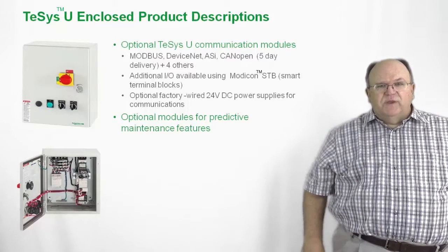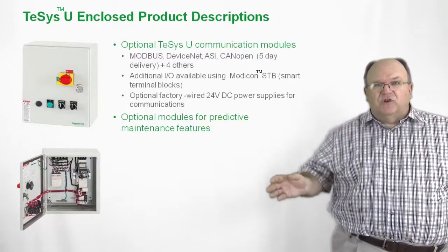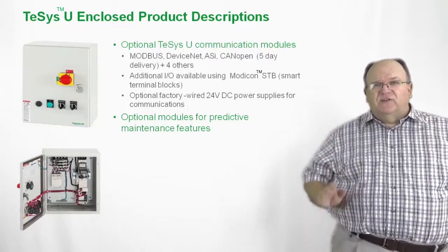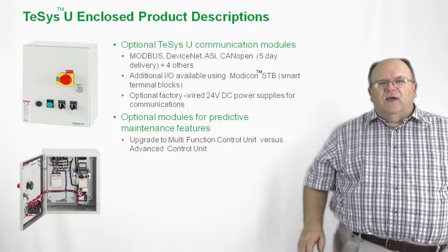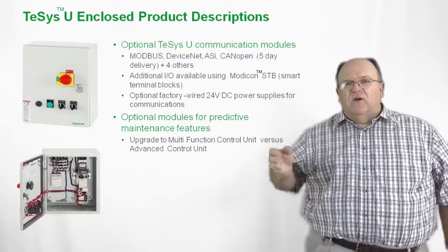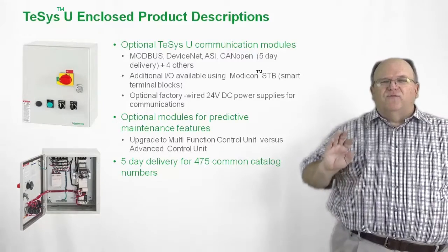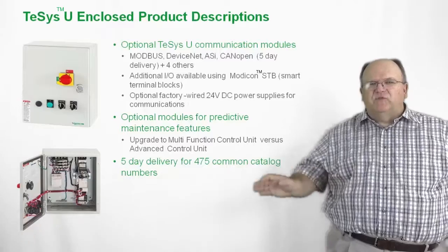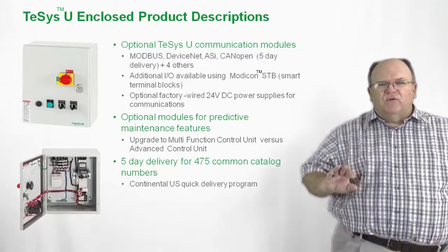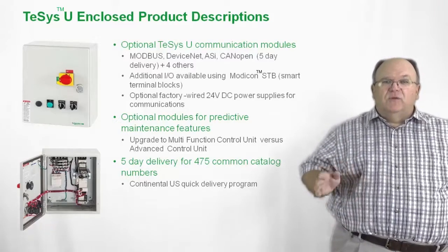When it comes to the control units, we can provide units that give you predictive maintenance features, such as being able to read the actual current draw of the motor, find out how many times the device has tripped, and get diagnostic information to tell you how the device tripped. You can upgrade to the multi-function unit in comparison to the standard or advanced control units to get all of these features. With a five-day lead time and over 475 common accessories and options available, everything is a quick-ship program in the US — so if you have a short turnaround job, you can do it with the TeSys U.